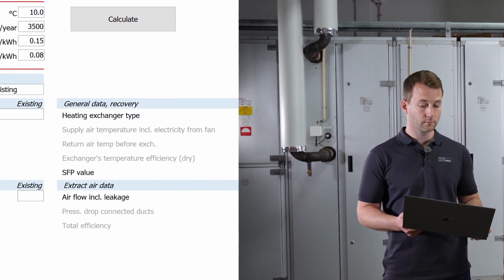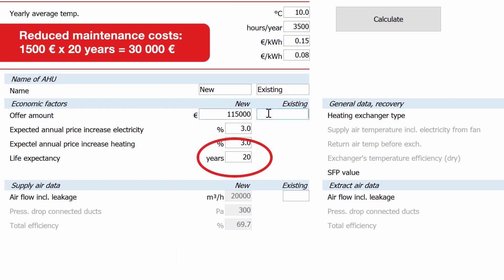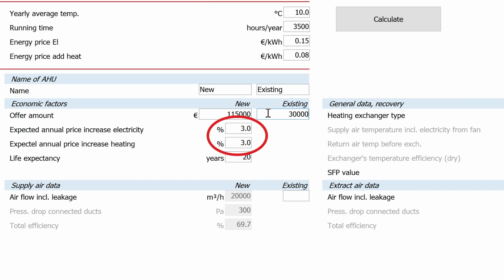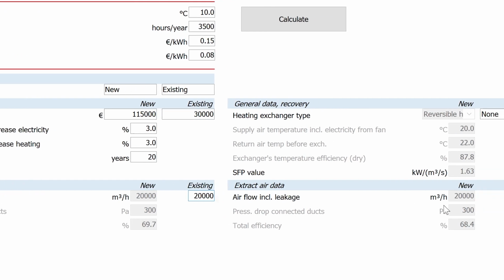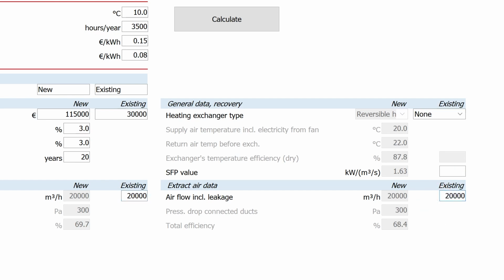The new unit will reduce maintenance cost. How much do you estimate that we will save? There will be reduced cost both when it comes to service and repairs. So I would say at least 1,500 euros a year. The life expectancy is set to 20 years. So we enter 30,000 euros here. We expect an annual price increase for electricity and heating of 3%. Here we enter the airflow for the existing unit. And the efficiency for the existing unit is 40%. For units from the 90s, the SFP value is usually about 3.5.